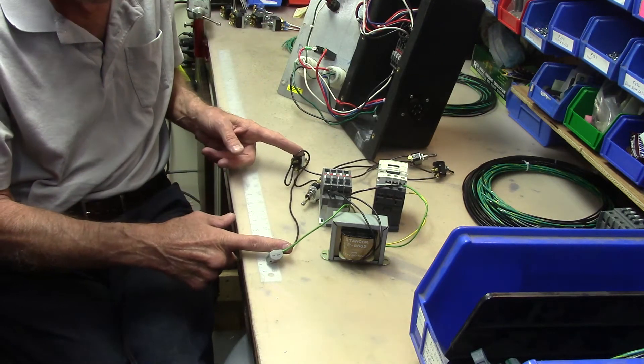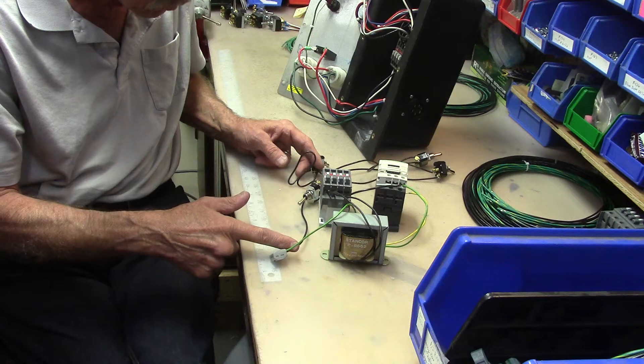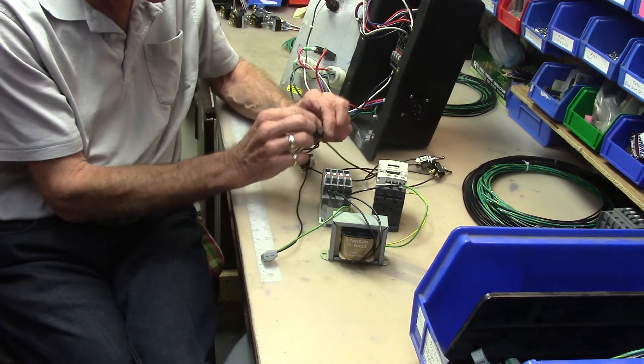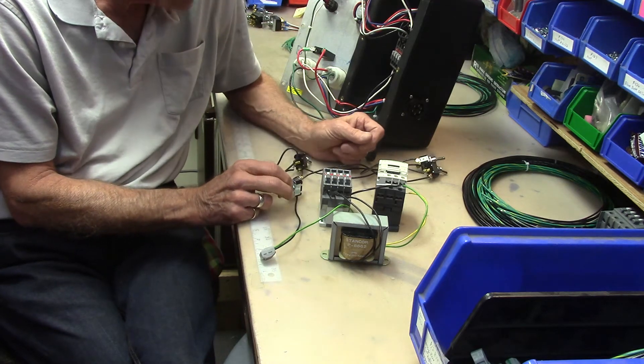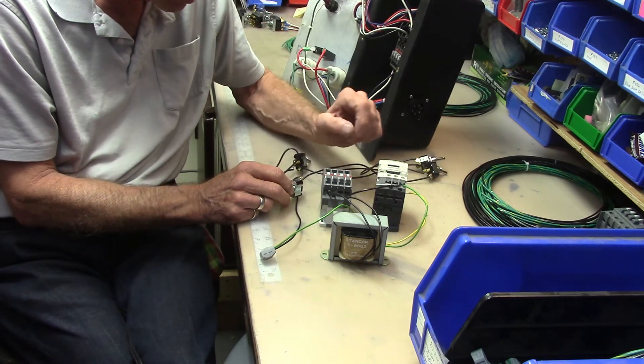You can ohms check these wires with your meter to see if there's good continuity. You can ohms check the switches to see if you have good continuity here. The last thing that I would suspect is an issue would be the contactor.